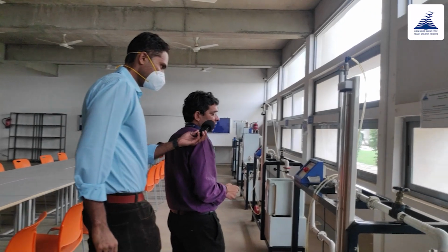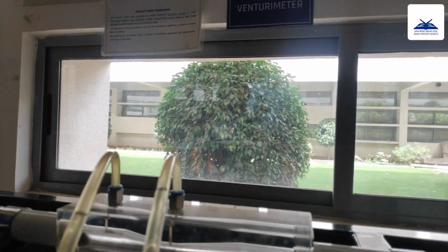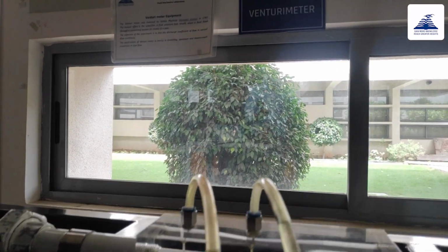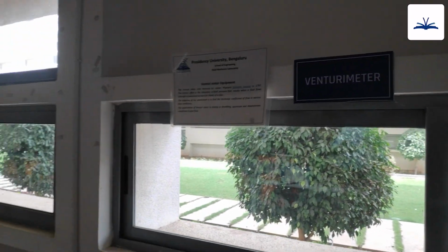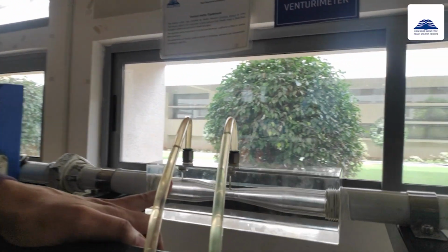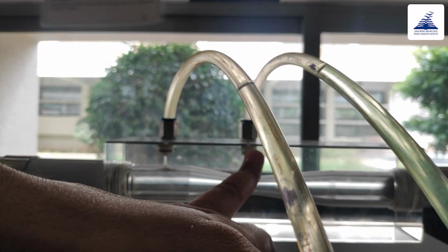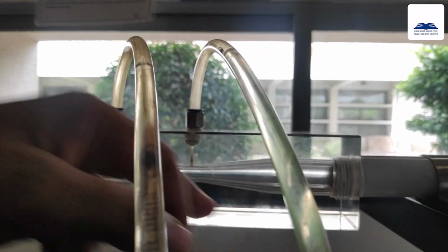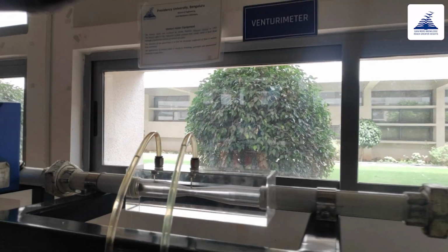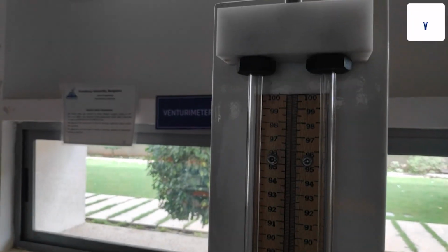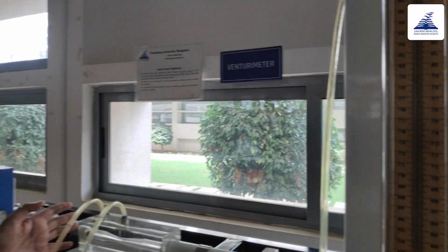This is a venturimeter. Again, this is used for flow measurement. The coefficient of discharge for this is around 0.9 to 0.95. You can see you have here the test section, the convergent nozzle, then here is your throat, then the divergent nozzle. You have a pressure measuring device connected through this U-tube manometer, so you can find out how much pressure difference is there. So these devices are generally used for flow measurement.